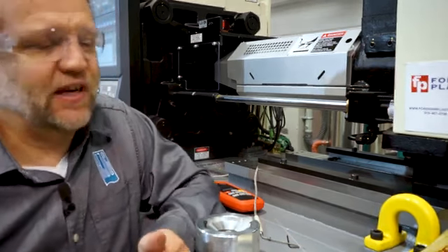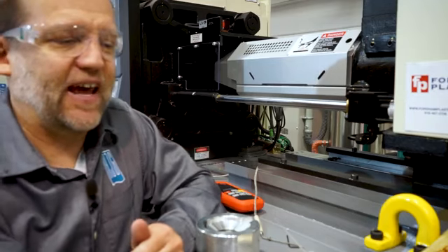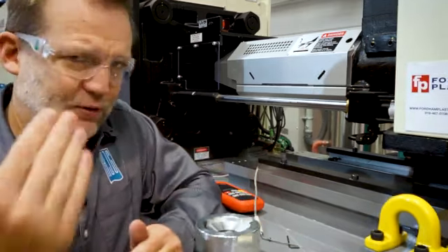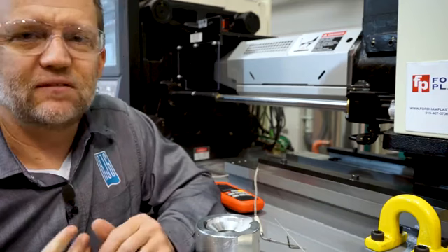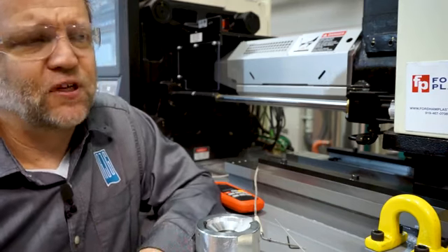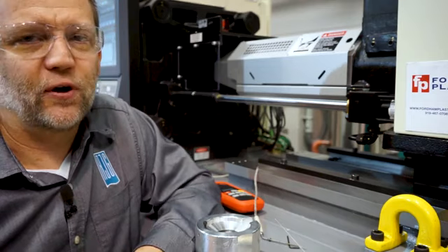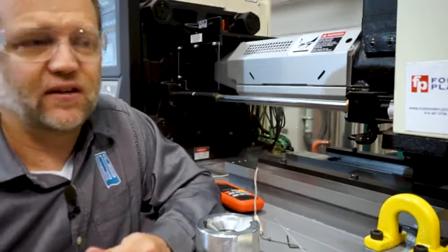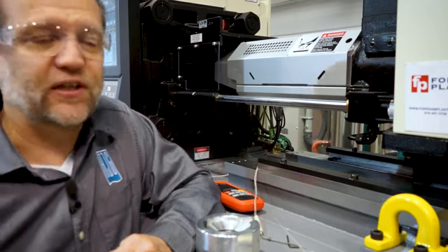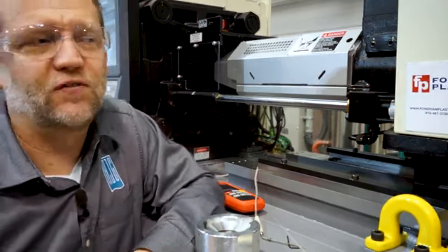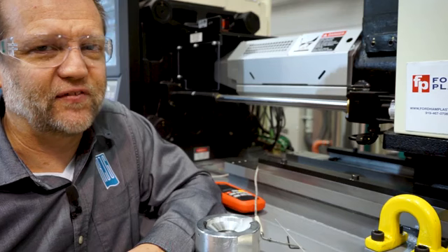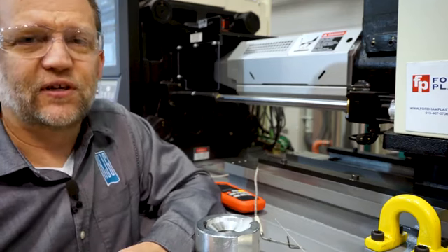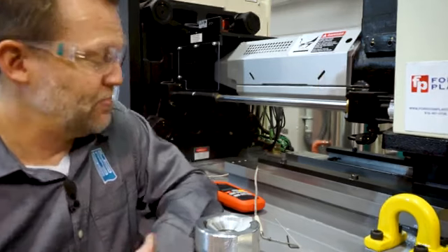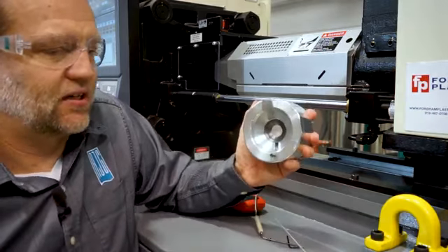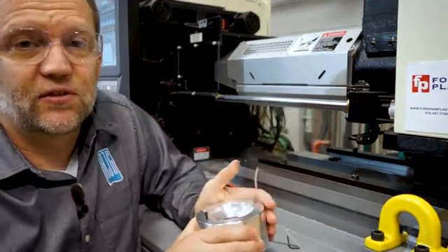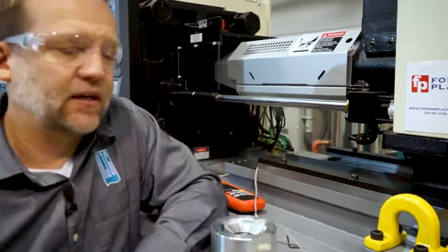If I did this two or three times in a row using just a handheld probe like this, and they were within 10 degrees of each other, I would consider that accurate enough. If you ever get a really weird reading, usually it's going to be too cold, do it again. And if it's drastically different, maybe you messed up the first time. If you get two, three readings in a row and you're within 5, 10 degrees, it's probably really close to the reading you're getting. If you use a device like this, the repeatability goes up, so the technique is more solid.